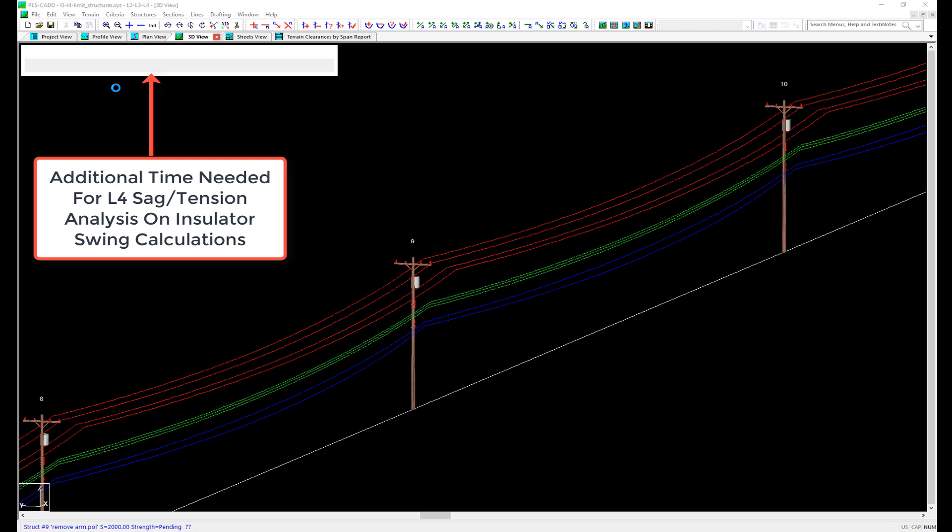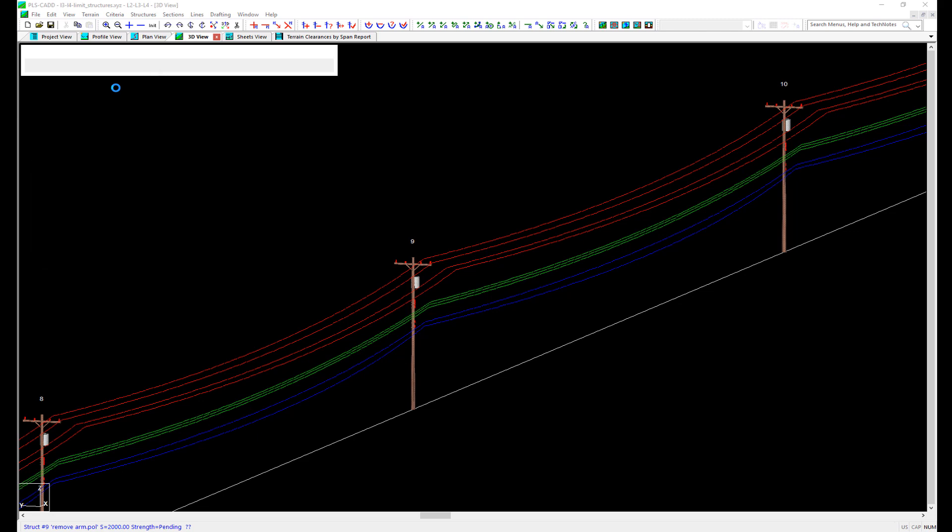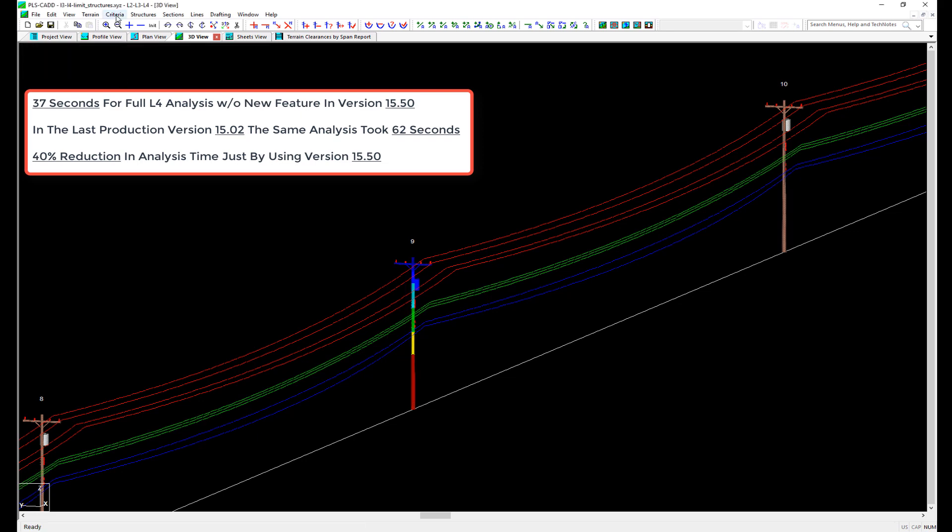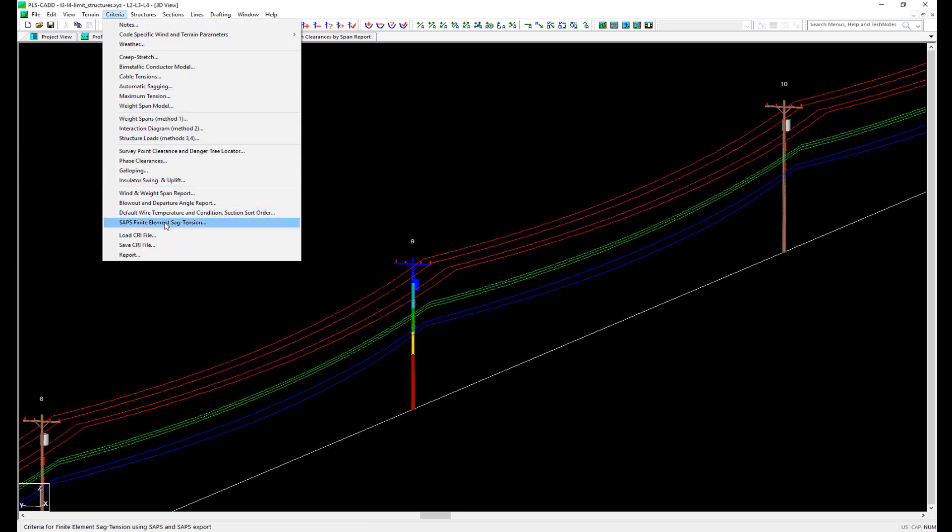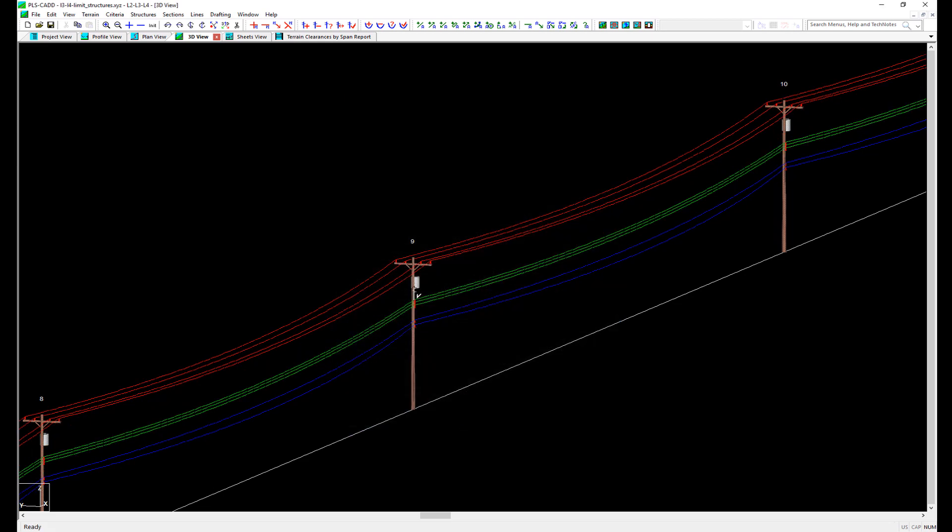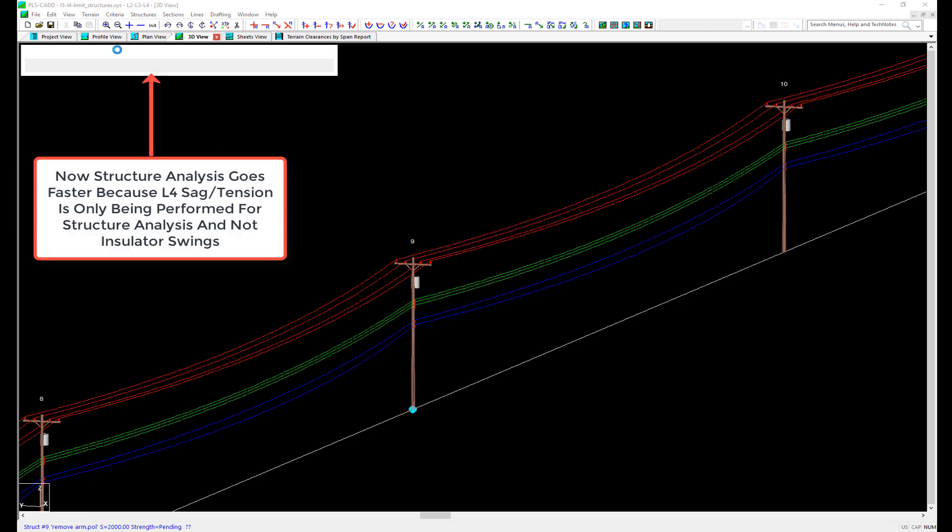Since most users are interested in structure utilization, you can perform a structure check command with this option, and it only calculates sag tension for loads when a structure check is performed, and not for the general display of the line. With this option not selected, even a simple line can take a few moments to update the display to show the position of the wire with the structures deflected. If we go back and enable this option, notice how the display updates instantly. And if we perform another structure check, we can see that it now runs significantly faster.